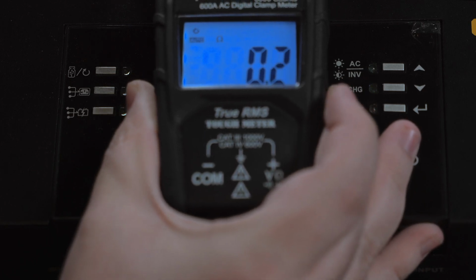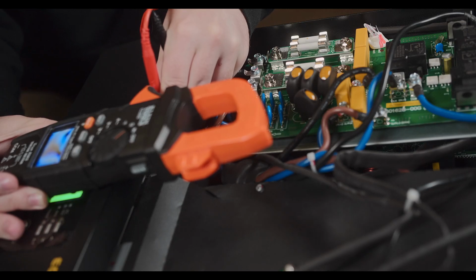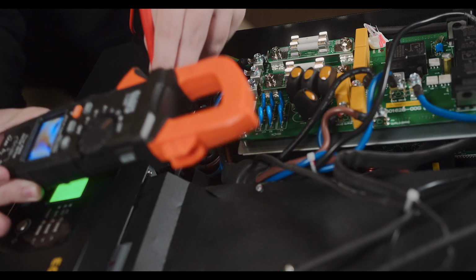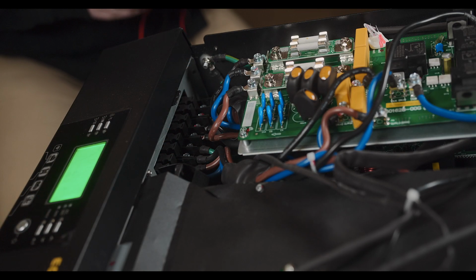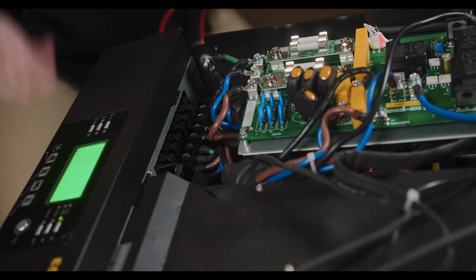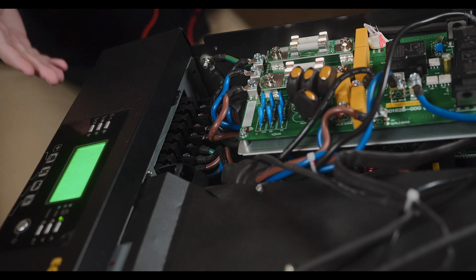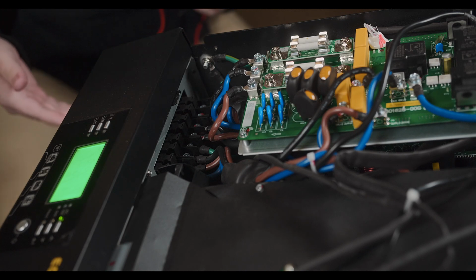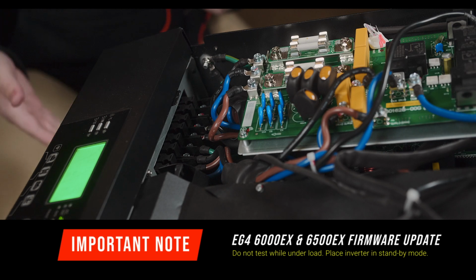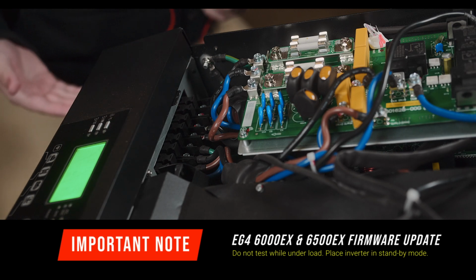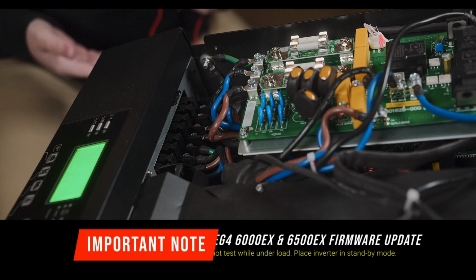That means if you have your ground neutral bond in a panel ahead of the unit, say coming from your grid source or service panel, you're going to have that neutral ground bond always in effect. It's important to note as well, if you're going to test continuity, that you do not test while under loads. In fact, it's a very safe bet to put your inverter in standby. You don't want to blow your multimeter.